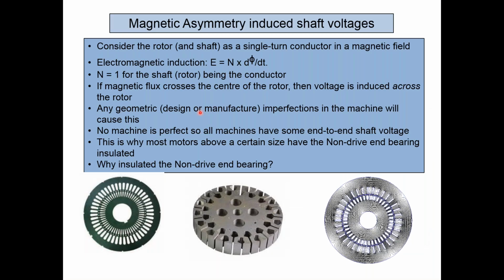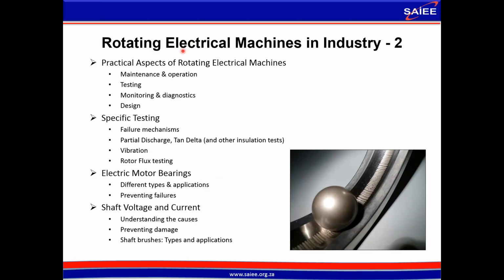Then this is an example of one of the slides from that part of the course, and it's on shaft voltages and currents. Why are shaft voltages and currents important? Because they are one of the primary causes of bearing failures. And then there's also a section on bearing failures. A little bit more detail of what we do. Maintenance and operation, as I said, it's getting the most out of your machines. So preventing failures.